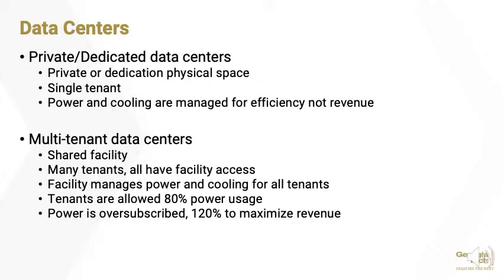Power is usually limited to about 80% of the maximum per tenant load to reduce the possibility of a power emergency. But the power within the data center as a whole is usually oversubscribed to 120%. This is to maximize revenue.